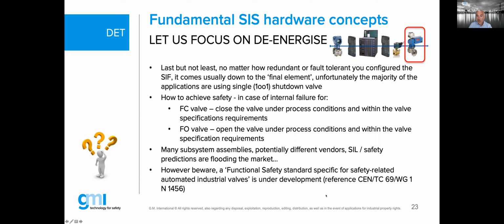That's here the reference of the work group. That's going to be a CEN standard. That's what they are working on. Because frankly speaking, what are we struggling with in our industry? How do we judge how reliable this is? Because it may be an assembly of subsystems, the body of the valve, the actuator of that valve, and maybe the positioner, maybe smart positioner of the valve, yes or no, are all maybe coming from different vendors. How can we predict the reliability of the subsystem, being your final element, if all different vendors are giving maybe no or maybe limited information? And that's where in our industry we need specific help.